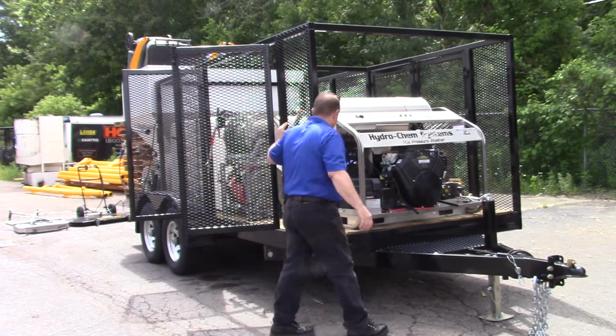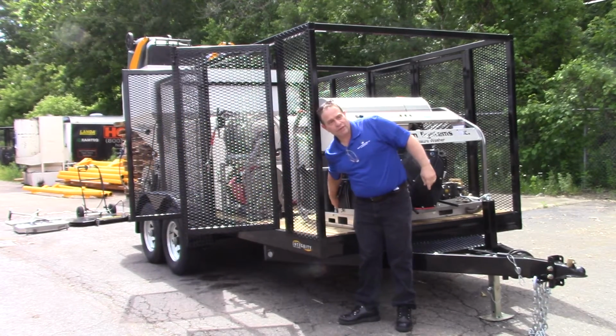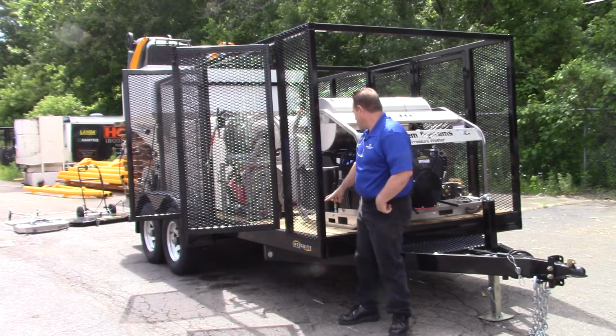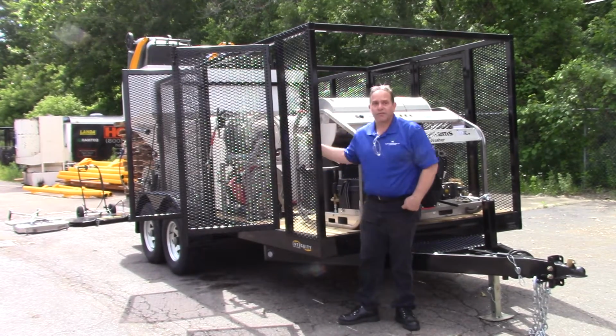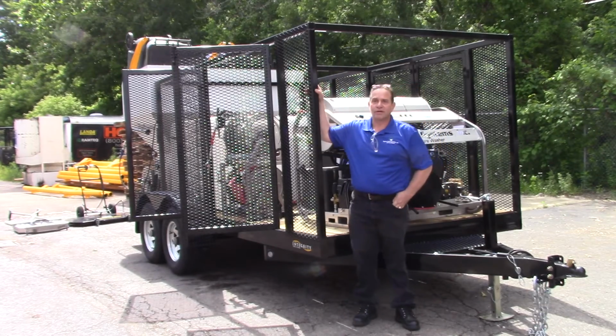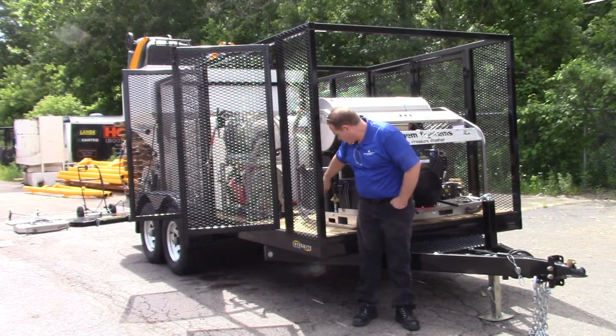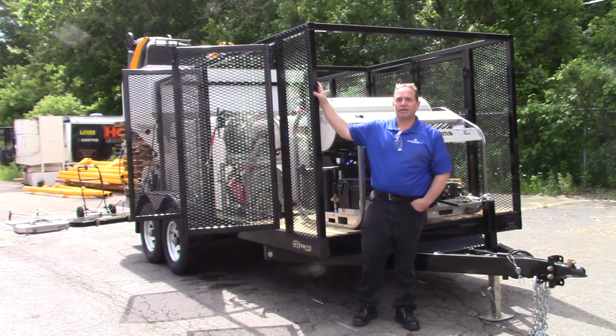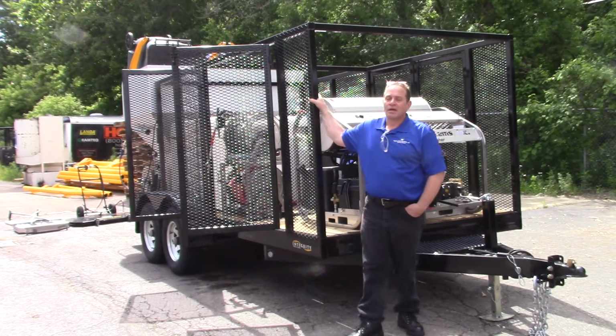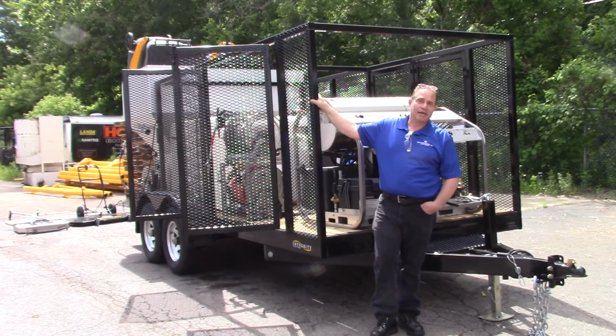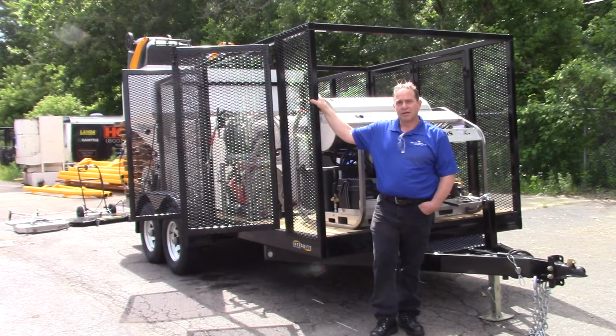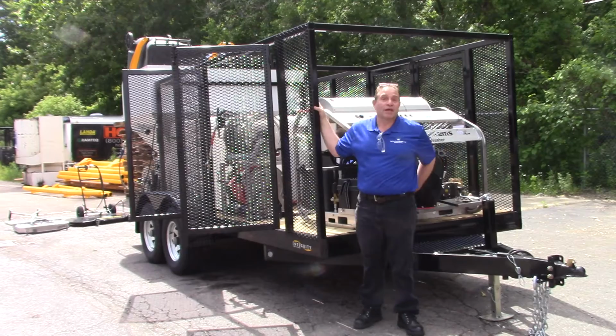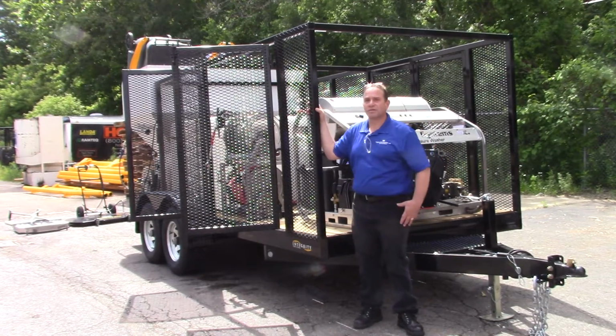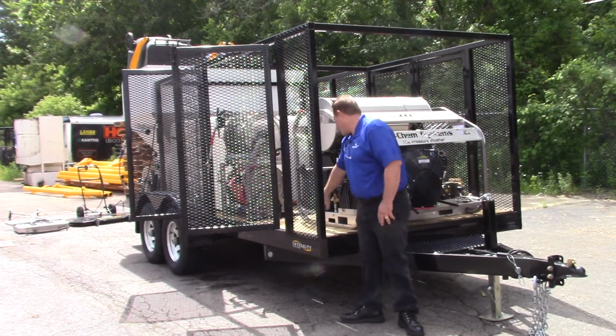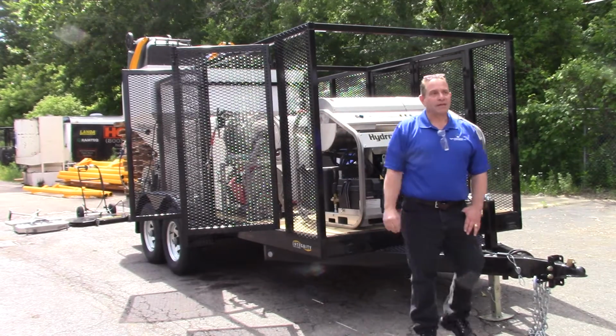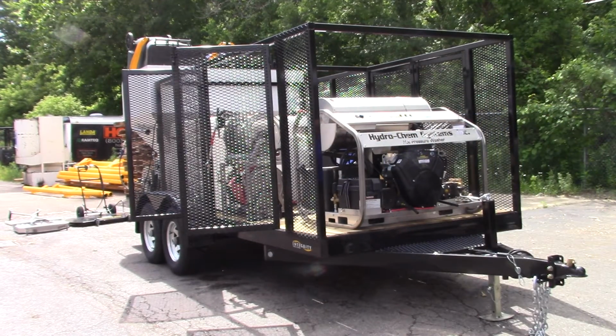Okay. And on top of that, you have pressure relief valves. There's normally two of them on here. The pressure relief is a spring-loaded little check valve. So you normally have one on the pressure side and then one on the discharge or in the burner area. Now on occasion, the spring can get loose and sometimes they'll pop off and leak. You can maybe adjust them slightly after a year or so, but normally that's an inexpensive replacement part. So you also have these extra down the line high pressure top off relief valves on there.